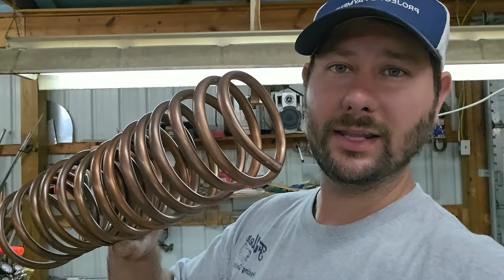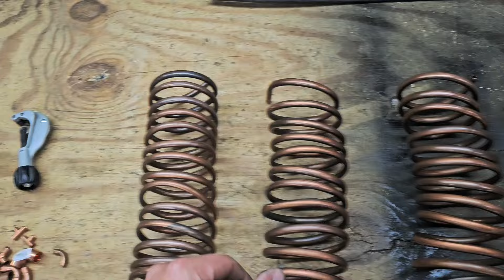Now that we've bent the copper into the shape that we're going to use for the coil, I'm going to show you the fittings and the tools I'm going to be using to make the whole assembly. We've got a set of oxyacetylene torches. I just finished taking my tubing cutters and cutting all the ends off of the little rolled up 3/8 copper coils that we've made. And I'm going to evenly space these out. And once I get them evenly spaced out to where I think I need them to stay, then I'm going to take a couple pieces of 3/8 copper, maybe one here at the bottom and one here at the top, and I'm going to braze those in so that this stays where it needs to stay.